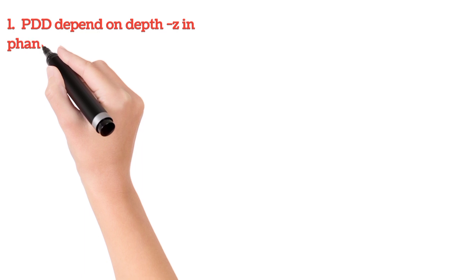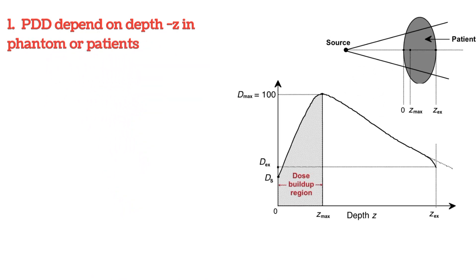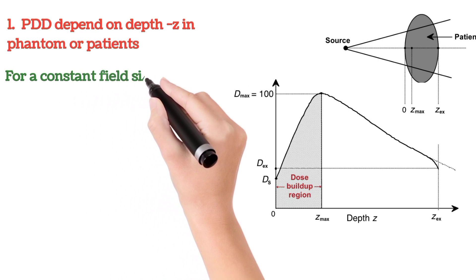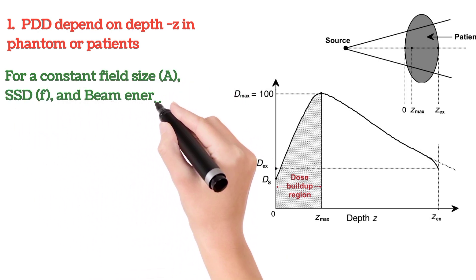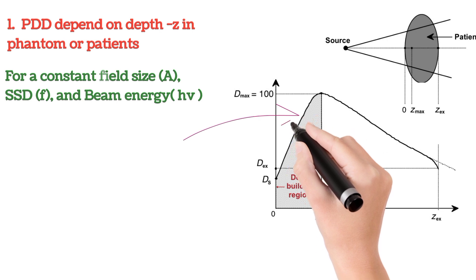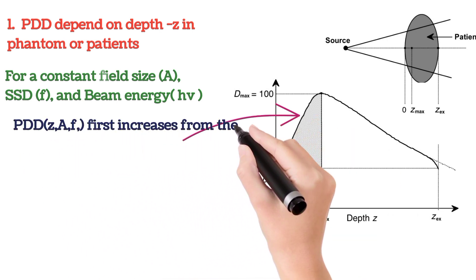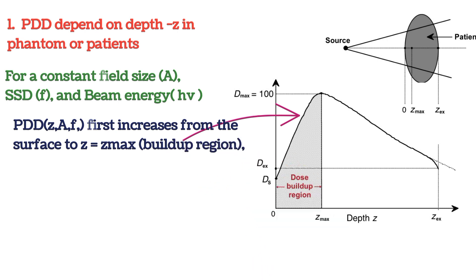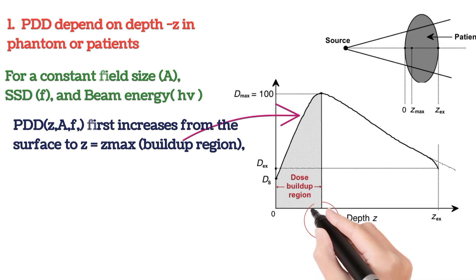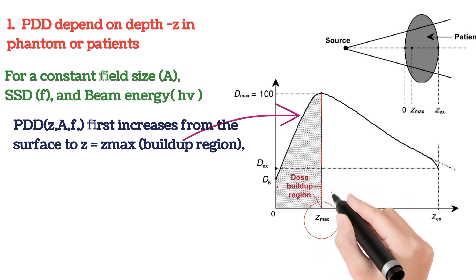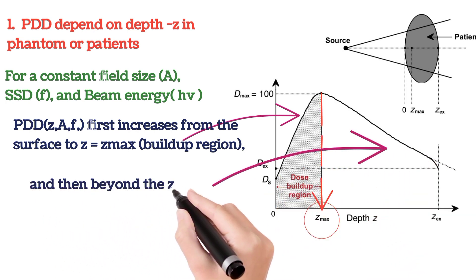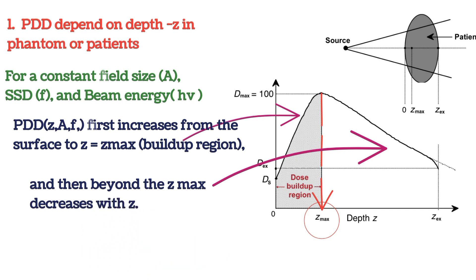We see how PDD depends on depth inside the phantom. For a constant field size, constant SSD, and fixed energy, PDD first increases with depth from the surface of the phantom to the depth of maximum dose. Here, Z max is the depth of maximum dose. Beyond Z max, PDD decreases with depth.